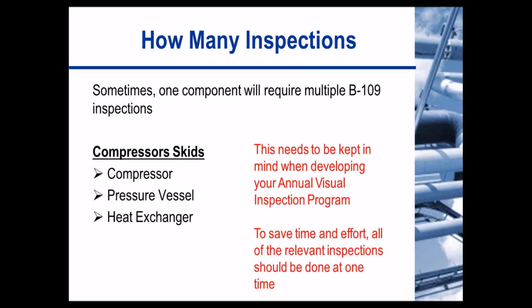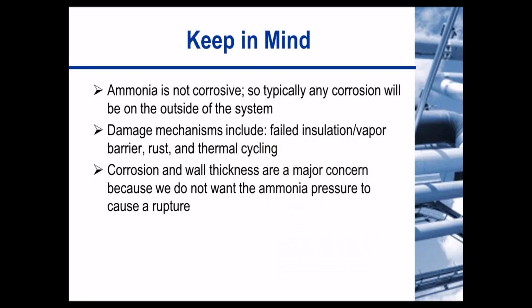Now, some things to keep in mind when doing your annual inspections. Ammonia is not corrosive, so typically any corrosion will be on the outside of the system. Damage mechanisms typically include failed insulation and vapor barriers, rust, microbial growth, and also thermal cycling. Corrosion and wall thickness are also a major concern because ammonia pressure can cause a rupture and a release into the community.